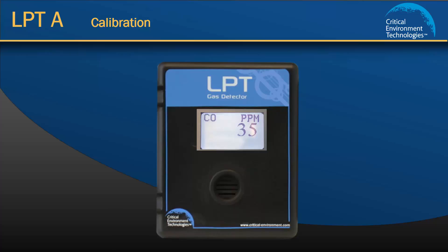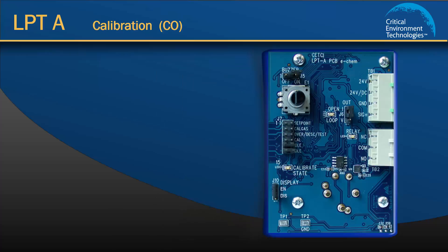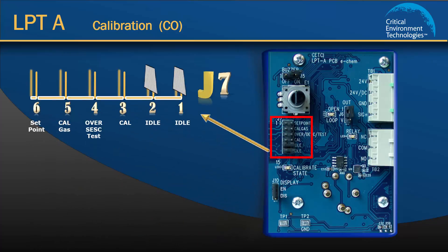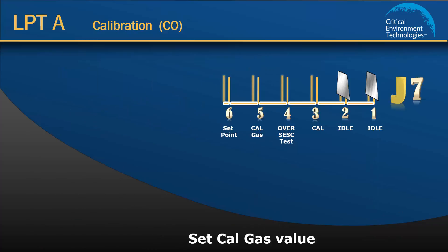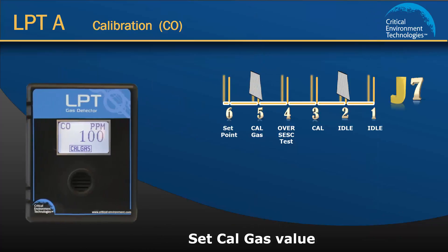The first step in calibration is to set the cal gas value. Open the LPTA and find the jumper bank on the left side of the board. To set the cal gas value, move one of the idle jumpers to position 5, cal gas.